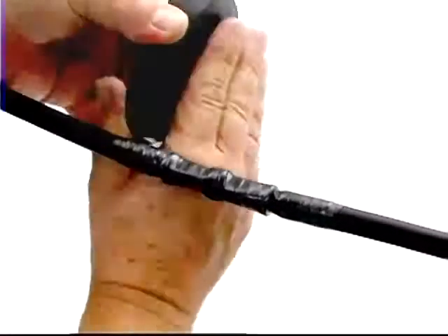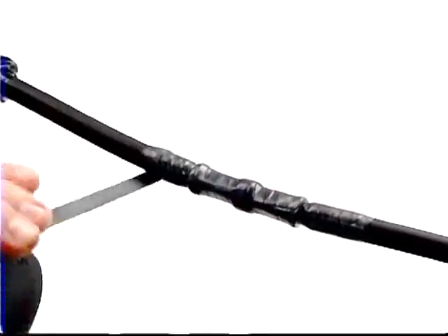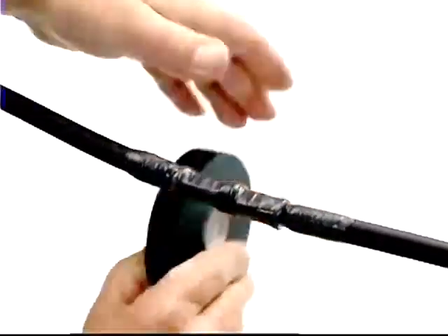For re-insulating a connection, the rule of thumb is that you should build up the tape insulation to one and one half times the existing cable insulation.